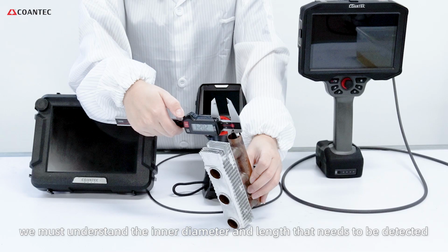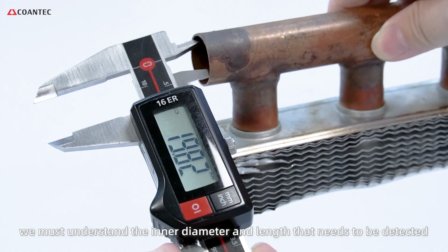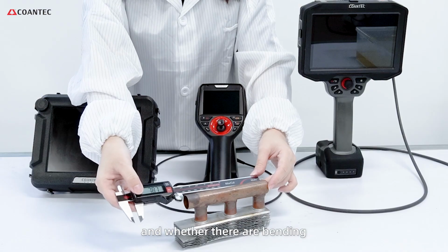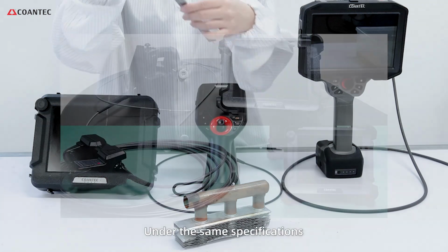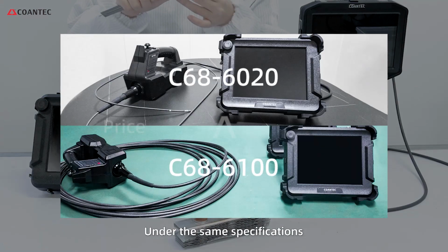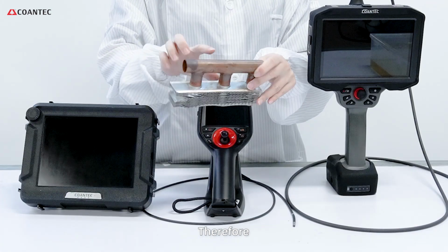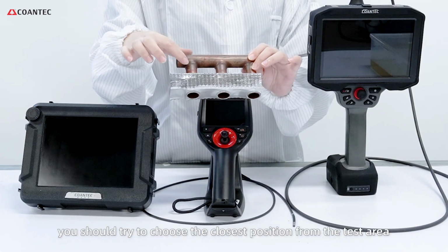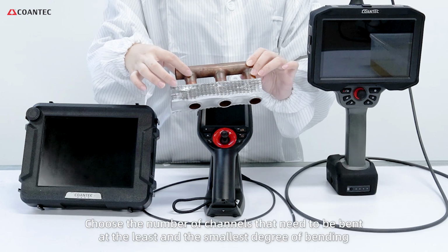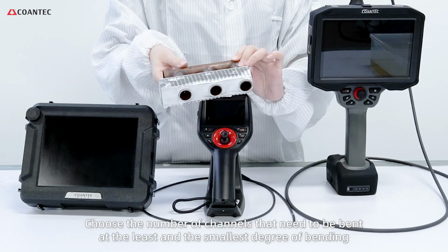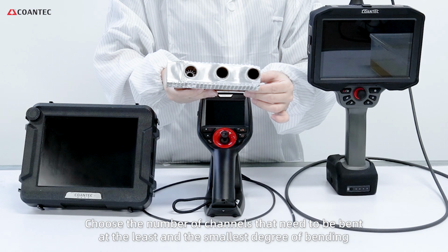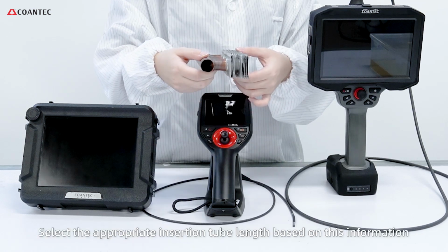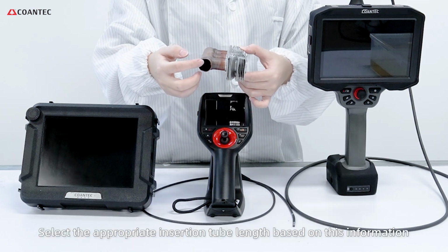Secondly, we must understand the inner diameter and length that needs to be detected, and whether there is bending. Under the same specifications, the longer the insertion tube, the higher the cost. Therefore, you should try to choose the closest position from the test area. Choose the channel that needs to be bent the least and with the smallest degree of bending. Select the appropriate insertion tube length based on this information.